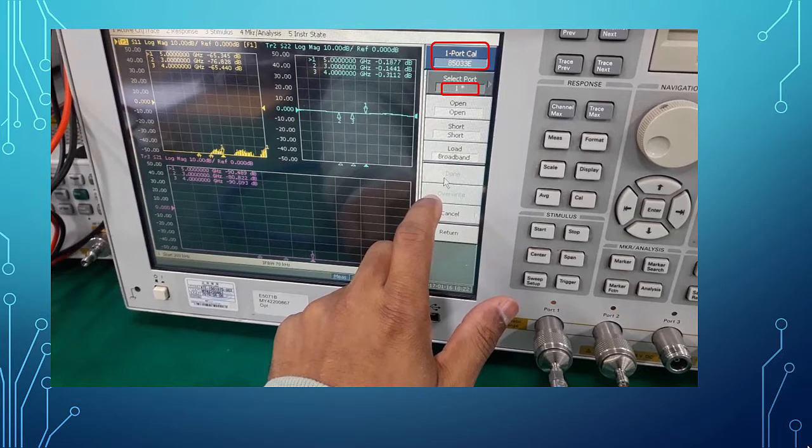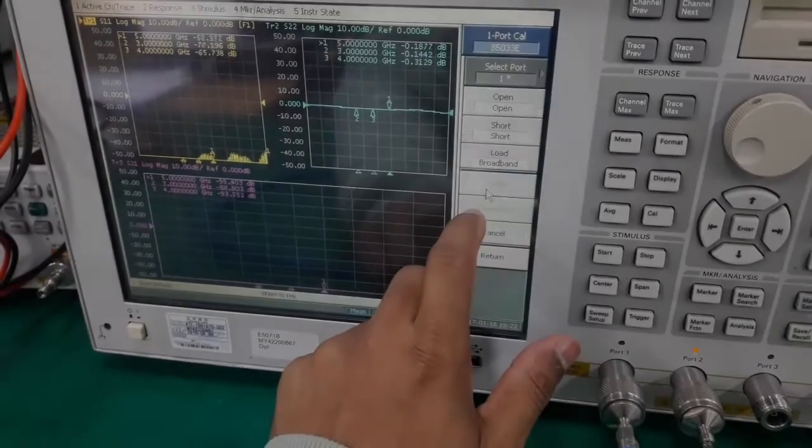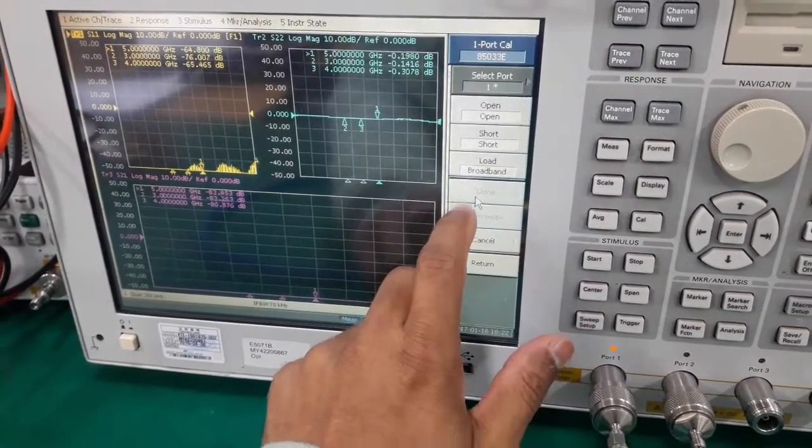After that, there are three options. Since the port 1 is connected to the load terminal, select load and a check mark appears. That means we are done with the load calibration.